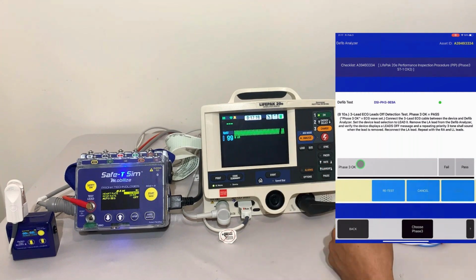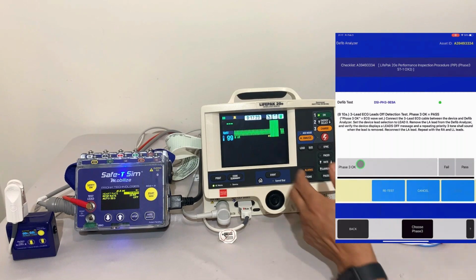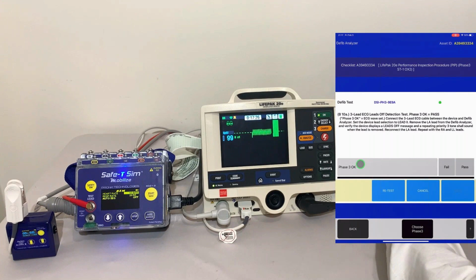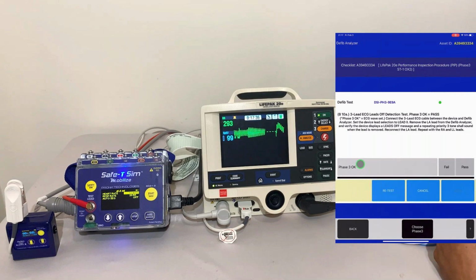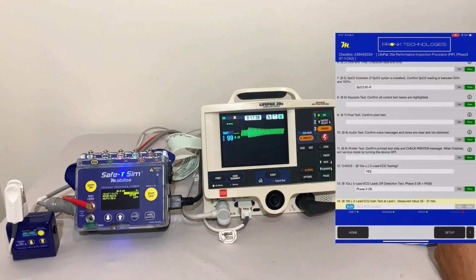We're simply going to disconnect a lead from the defib analyzer to confirm it can detect the lead has been removed. I want to do this for each and every lead, so I'm going to repeat that for the 2 leads, confirming that for each one we're getting a leads off detection message. We can see that we are. So that test is good, it passes, go on to the next test.